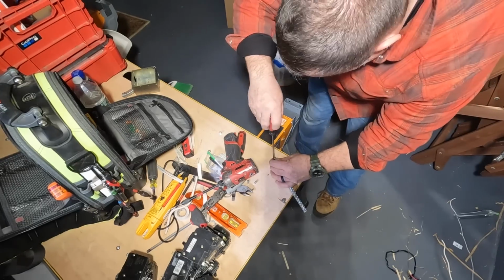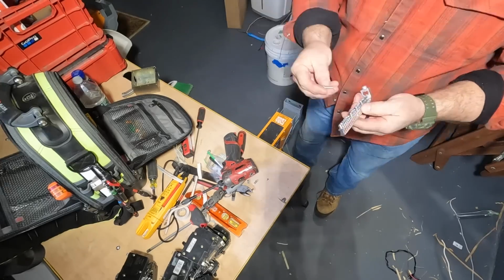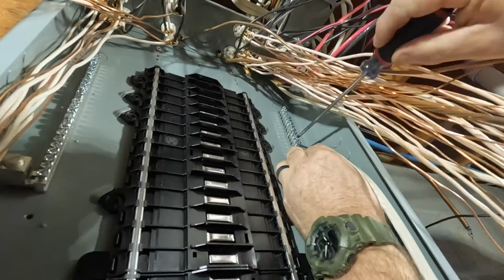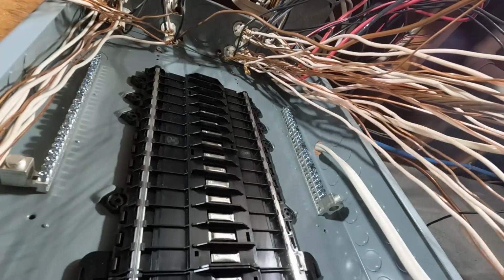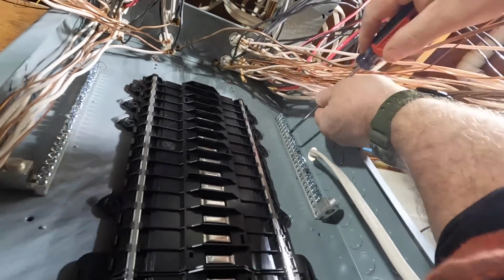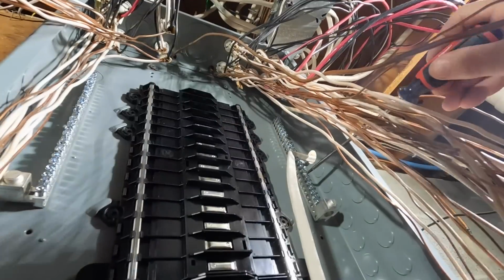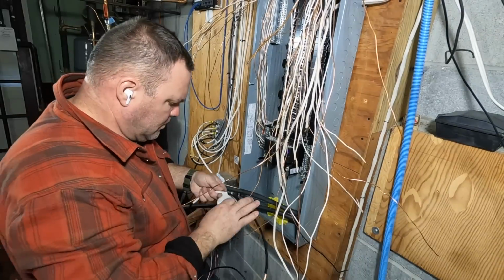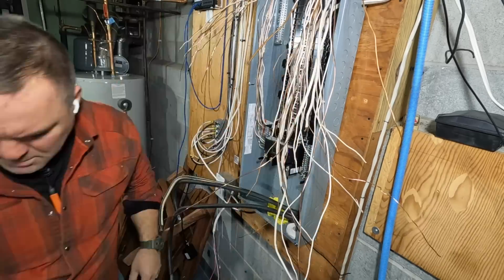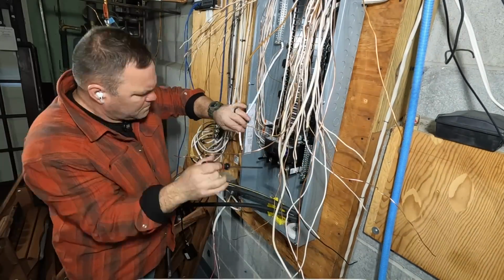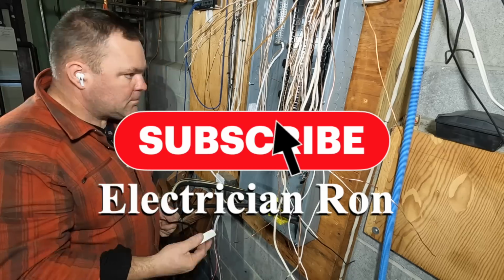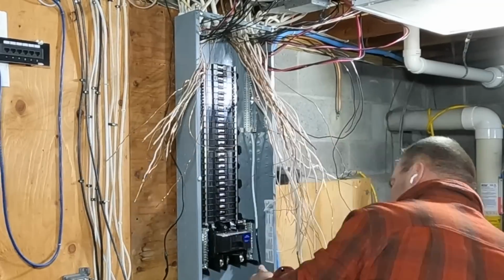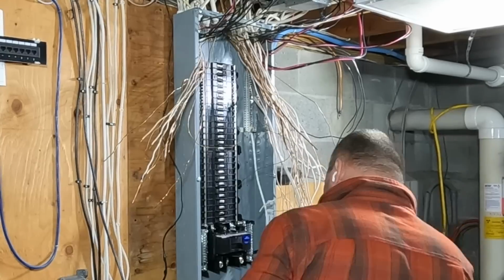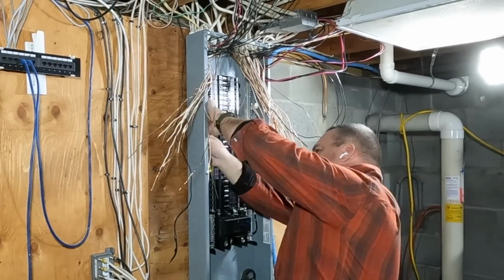NEC section 250.4 will explain that to you, especially A 1 through 5. NEC article 250.4, the general requirements for grounding and bonding. The following general requirements identify what grounding and bonding of electrical systems are required to accomplish. The prescriptive methods contained in Article 250 shall be followed to comply with the performance requirements of this section. A. Grounded systems. 1. Electrical system grounding. Electrical systems that are grounded shall be connected to earth in a manner that will limit the voltage imposed by lightning, line surges, or unintentional contact with higher voltage lines, and that will stabilize the voltage to earth during normal operation. 250.4(A)(2), grounding of electrical equipment.